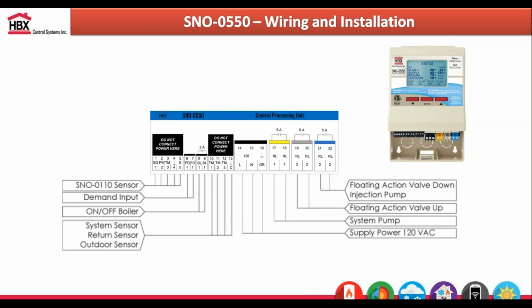and that shield wire will need to go in terminal 5. Again, if you ever get a wonky reading for your slab temperature, it's usually because you put a wire into the wrong terminal. If you do this, it doesn't cause damage to those connectors or anything like that. It just gives you an off reading, letting you know you've wired something incorrectly. Just wire it up correctly, and then you get a correct temperature reading.